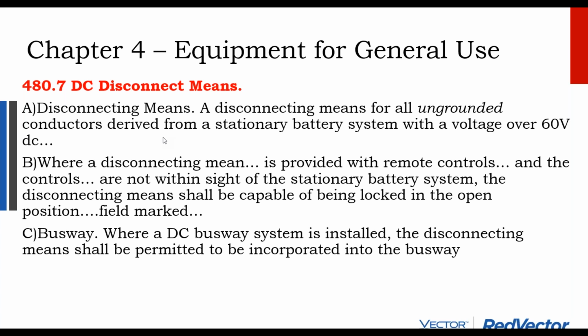Let's talk about the DC disconnect. We have to have a disconnecting means for all ungrounded conductors coming out of a battery with a voltage of over 60 volts. So many battery banks are 48 volts nominal. And so the disconnecting means is not required right off the bat for the battery, although as we'll see later, pretty much whenever the battery is more than 5 feet away of where it's being plugged into, you need a disconnecting means. And then just because you're not required to have a disconnect, it's still a very good idea to have a disconnect. If you want to service the equipment and de-energize the equipment, the disconnect is there.